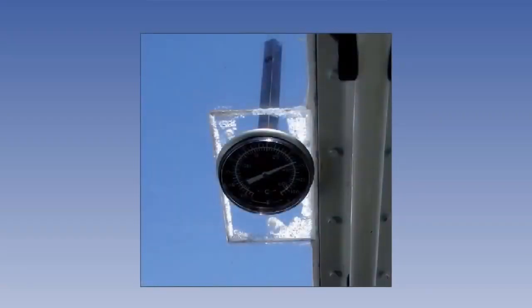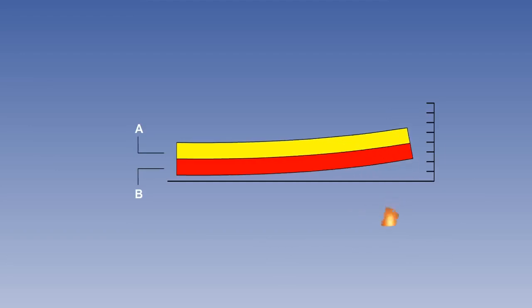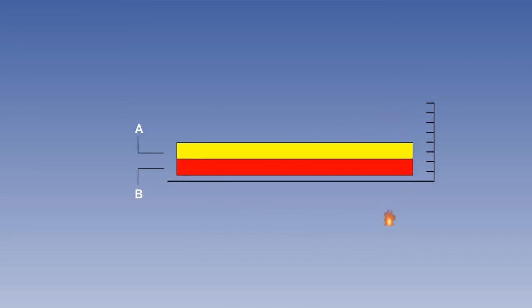Air temperature thermometers can be divided into two basic types: the direct reading thermometer and the remote reading thermometer. One of the simplest is the bimetallic thermometer, and it works on the principle that two metals with different coefficients of expansion will expand at different rates if subjected to heat. If these two metals are bonded together to form a single bimetallic strip, the metal with the greater rate of expansion will cause the bimetallic strip to bend.